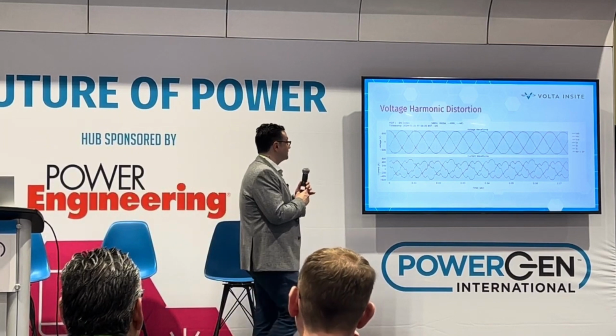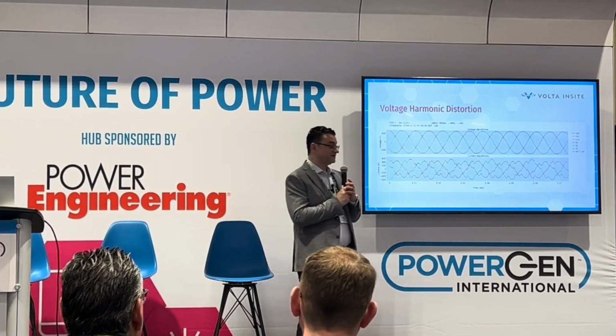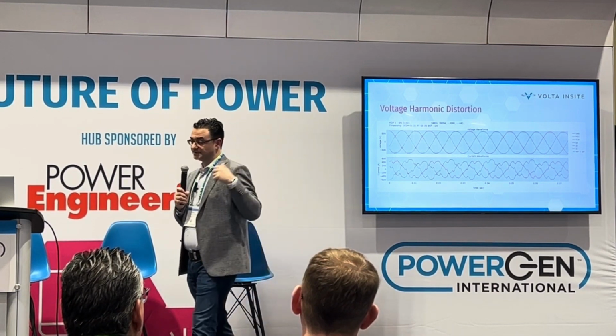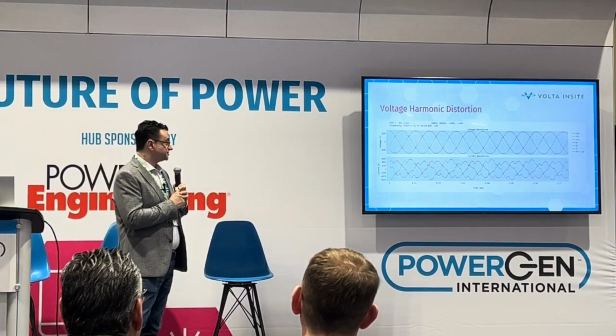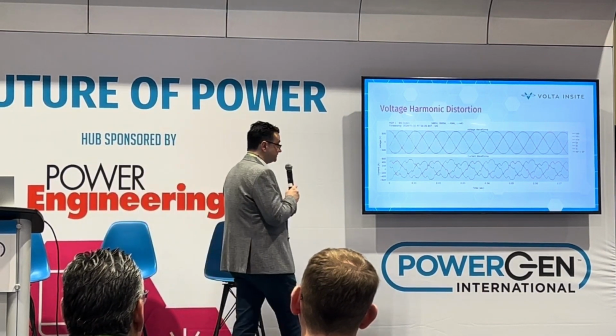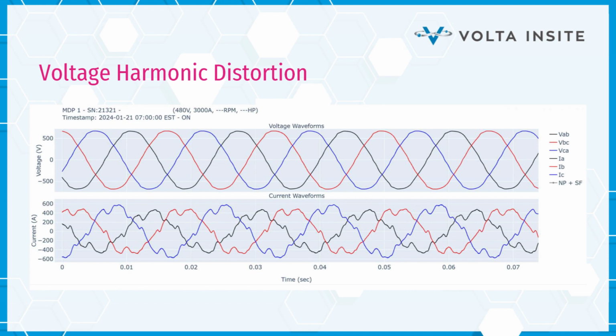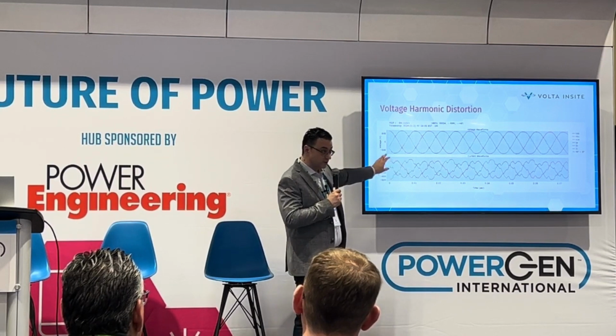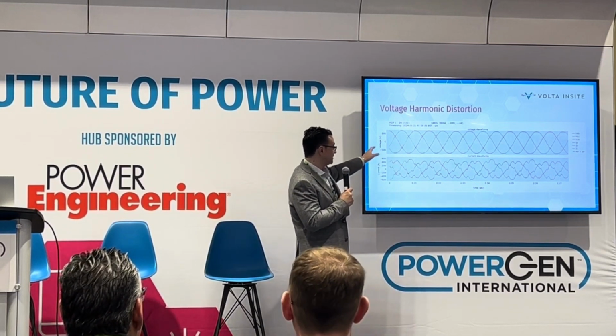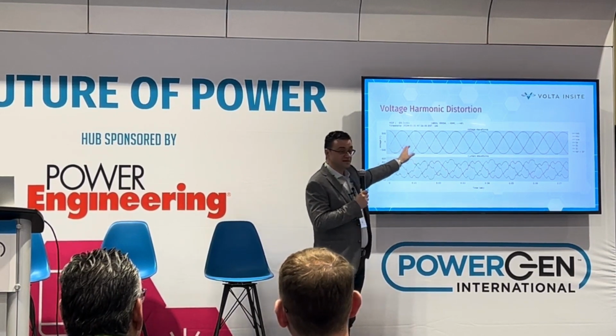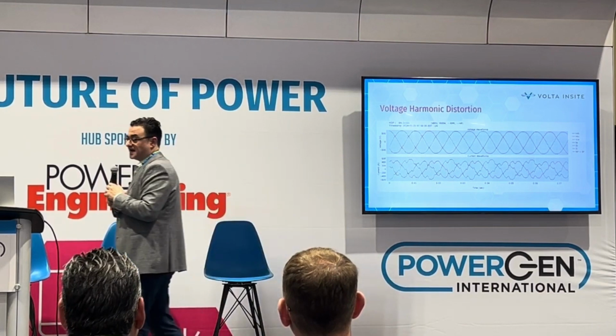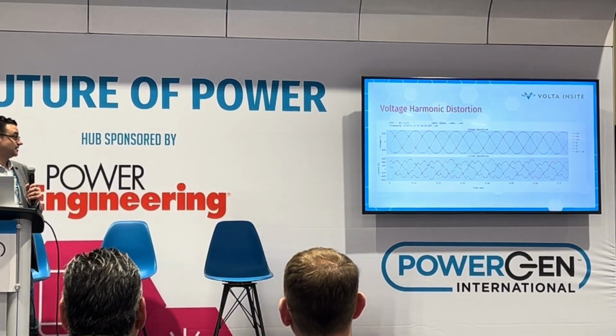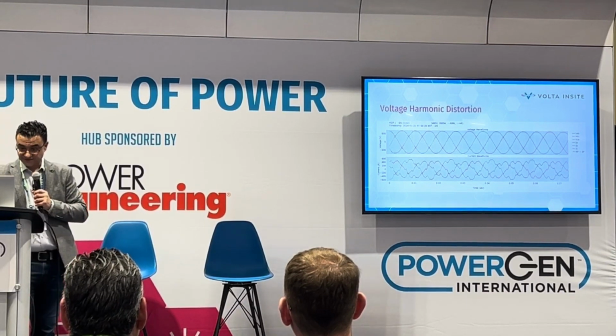Here's another example of harmonic equipment. Our monitoring equipment is actually deployed on a piece of switchgear, which is feeding about 100 VFDs. Now, the VFDs, the front end of the VFDs are doing some form of power factor correction as they're running, and they're creating this waveform, which is pretty significant. You're seeing peaks of 600 amps. And because of the harmonic distortion in the waveform, we're also slightly distorting the voltage as well. That is not a pure sinusoid anymore. So it's important to understand what is happening at your distribution side in order to maintain good voltage stability.